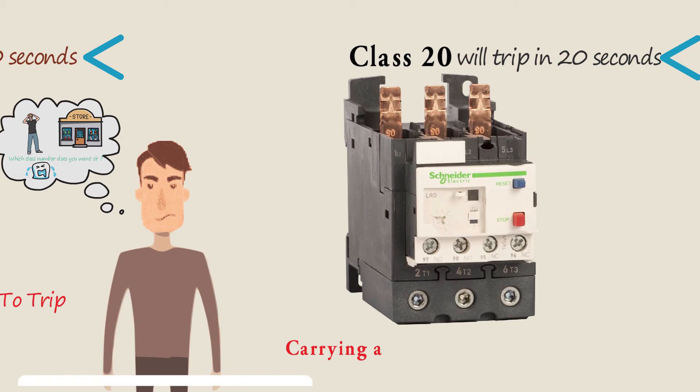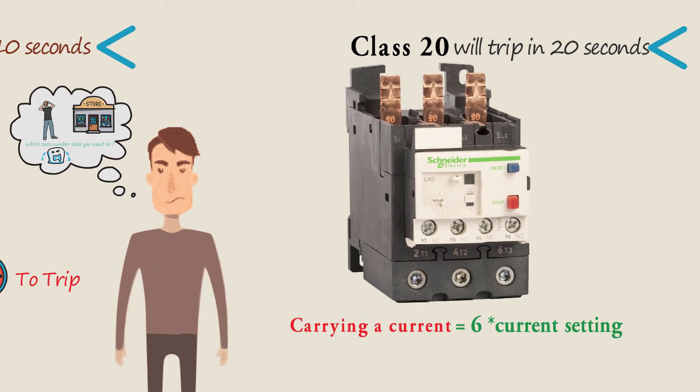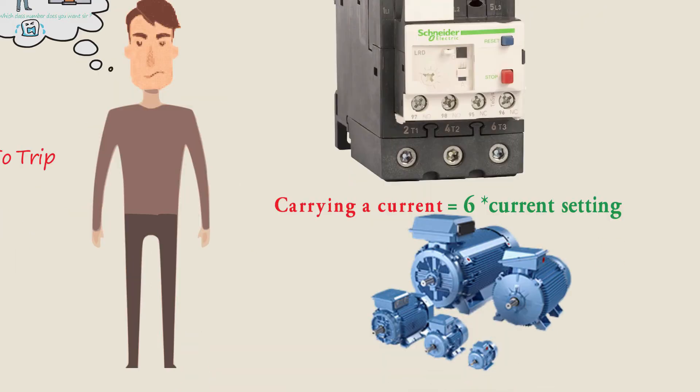A Class 20 relay will trip in 20 seconds or less when carrying a current equal to six times its rating. A Class 20 overload relay would be suitable for applications with high initial loads.